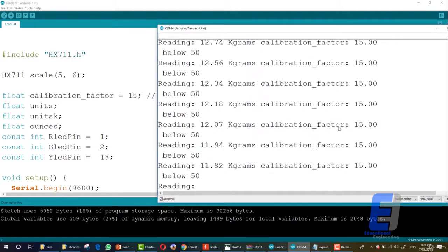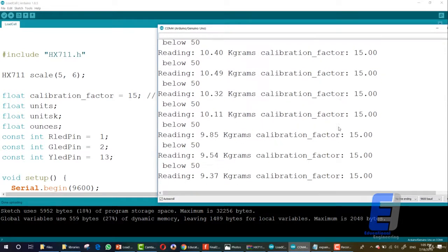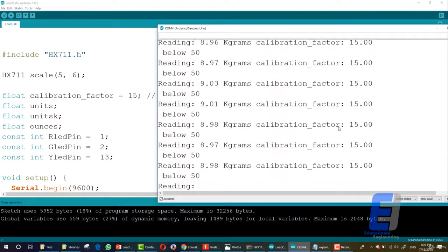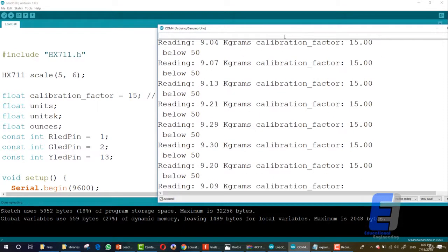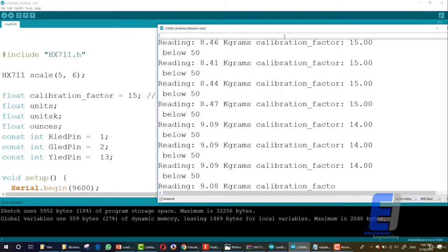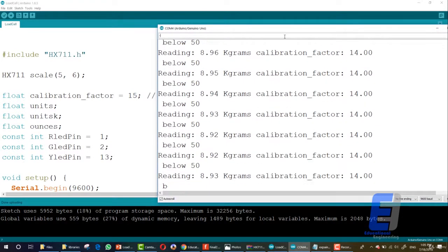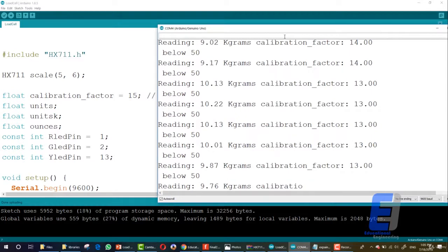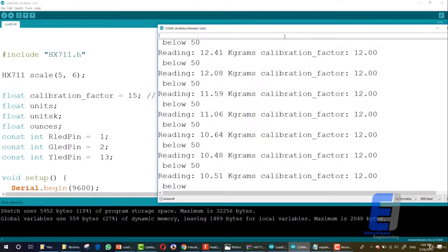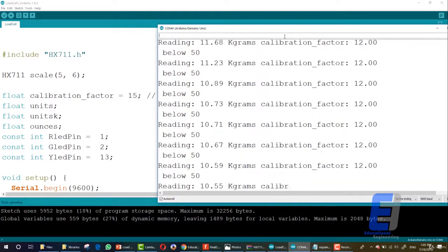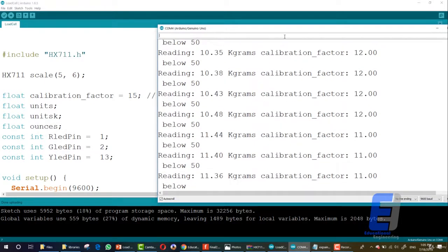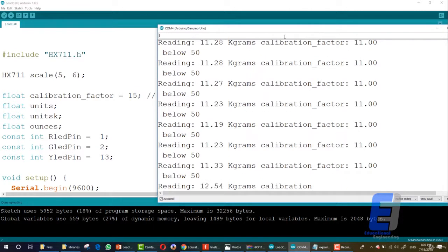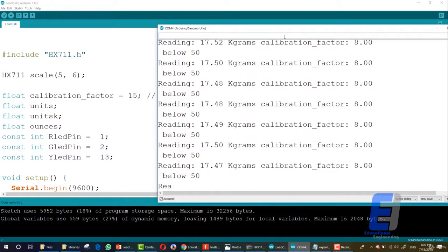While the weight that I placed on this load cell isn't even close to these numbers. So what you will need to do is either click plus or minus here to increase or decrease the calibration factor. And since I already know that my load cell calibration factor is like eight, I will keep going down until I reach eight. And now it's displaying exactly what I'm placing.